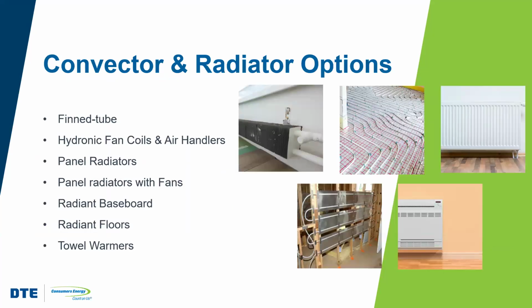There are many types of convectors and radiators that could be used for the system. We want to make sure that we match those emitters to the system. Some are well suited to systems with certain traits, with higher temperatures or lower temperatures. For example, if you've got a low temperature system, 90-degree water, 120-degree water, that's okay for radiant slabs and floor systems, but it's not okay for fan coil convectors or radiant panel heaters, right? Or for fin tube, right? For fin tube, for example, we want to use that is best suited to higher temperature systems. So 160 degrees to 200 degrees, right? That's also great for the radiant baseboard.